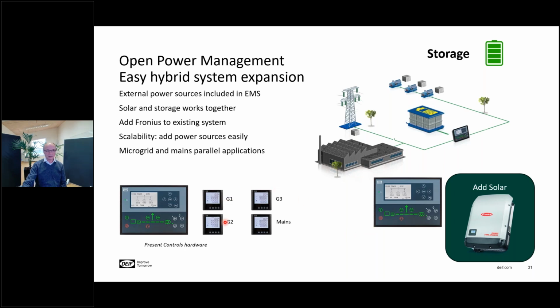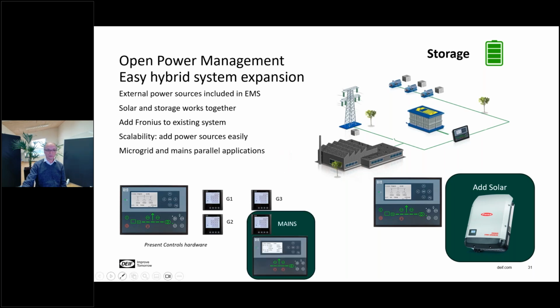You can see I've shown the power meters also mentioned by Jakob. We need to measure what's happening on the generators, what's happening on the utility still. You also have the possibility, for increased functionality, to install an AGC mains in your system, so you move closer towards the full power management system.